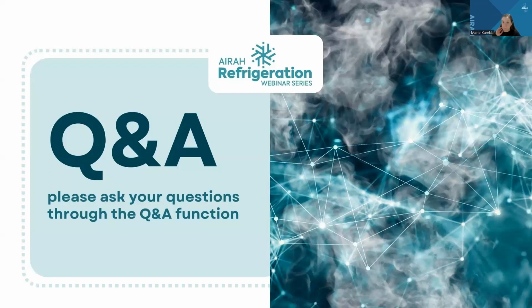Yeah, sure. Next one here is, what's a pragmatic approach for sizing the system? How much allowance or safety factor for peak times and peak loads, etc.? Again, it's for judgment. A lot of people use 10-20% as a safety factor. And the other thing is the software that are often used.